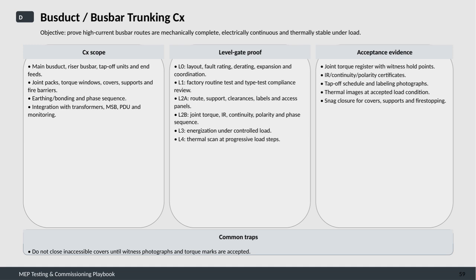Levels 2A and 2B cover physical installation checks like routing, supports, clearances, labeling, joint torque verification, insulation resistance, continuity, polarity, and phase sequence. Level 3 involves energizing the system under controlled load, and Level 4 consists of thermal scanning at progressive load steps to confirm thermal stability.